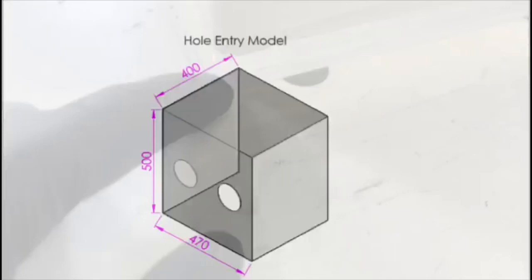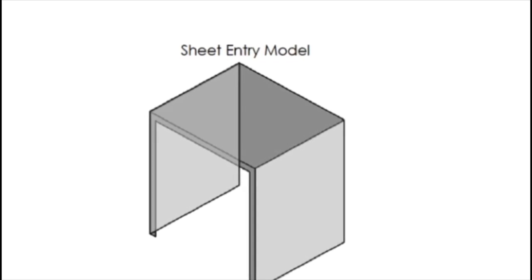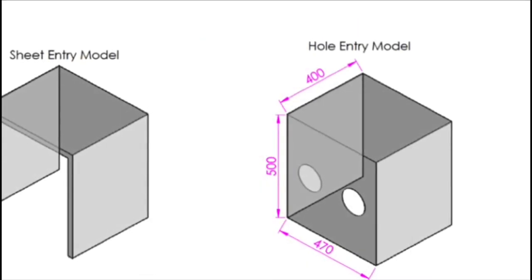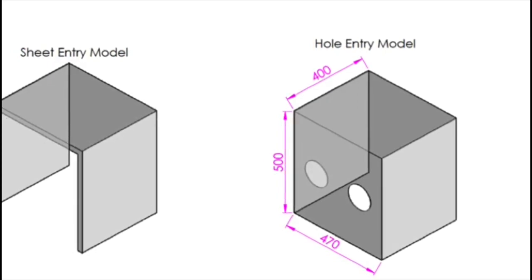It's made from two pieces of material and the top piece has a little track in it. That track will be filled with glue so you can wash it down after a procedure. The top surface is now on the bottom drying, giving a nice smooth surface all the way around — quite easily cleaned. This little lip will make it easy to lift on and lift off. There are two different design variants: one has an opening on the caudal end but just hand holes on the cranial end. The second design has an opening on both ends, with the large opening covered by a transparent surgical sheet.